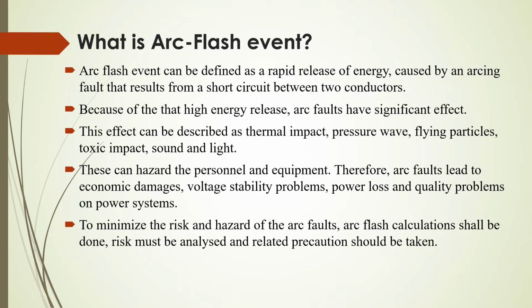So friends, let's see. What is an arc flash event? Arc flash event can be defined as a rapid release of energy caused by an arcing fault that results from a short circuit between two conductors. Because of that high energy release, arc faults have significant effects. These effects can be described as thermal impact, pressure wave, flying particles, toxic impact, sound and light. These can hazard the personnel and equipment. Therefore, arc faults lead to economic damages, voltage stability problems, power loss and quality problems on power systems.